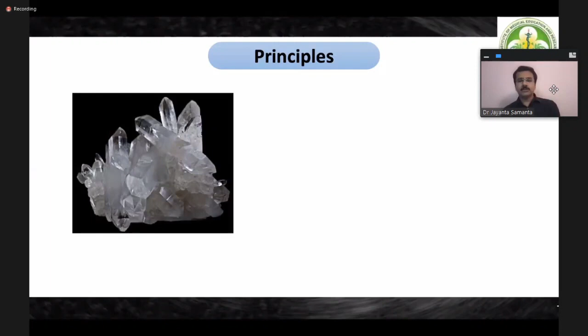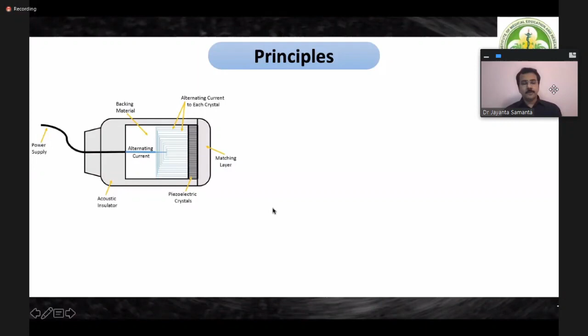Even for a transabdominal ultrasound, just behind the matching layer there will be a layer where the piezoelectric crystals are kept. When an electrical impulse comes, the piezoelectric crystal starts vibrating. It generates ultrasonic waves that go through the tissues and get reflected variably from various parts of the tissues in various frequencies, hit the piezoelectric crystals again, and that gets transformed into an electrical impulse and gives us an image on a monitor. So these piezoelectric crystals act both as a sender of the ultrasonic waves as well as the receiver.